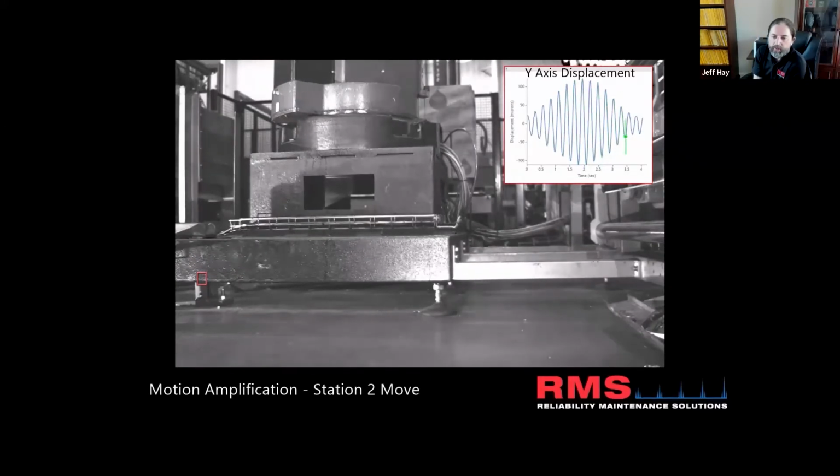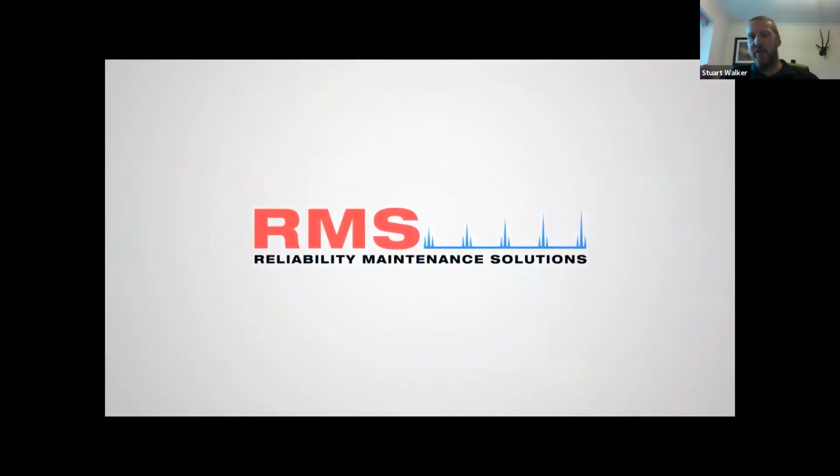Someone says, could we record the motion amplification of the pump during coast down and assess the critical speeds and resonance? Absolutely, totally do that. What's nice when you do a rundown or coast down and draw an ROI, a region of interest, and get a spectrum, it's a bit like peak hold. It holds across that range, so you end up with a graph that shows you where the highest vibration was at what frequency. You could also pull in the waveform, select a region and have a spectrum of that, but you'll need many samples to do that. And you get the full field during that coast down, so you don't have to pick and choose.